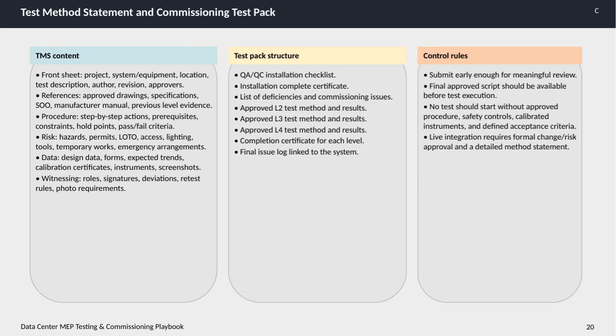On this slide, we're diving into the structure and control rules for the test method statement and commissioning test pack, key components in our data center MEP testing and commissioning playbook. Starting with the test method statement, or TMS, it's designed to be a comprehensive document that ensures clarity and safety throughout the testing process. It begins with a front sheet capturing essential details like the project name, specific systems or equipment being tested, location, a description of the test, the author, revision number, and approvers. This sets the context and accountability right from the start.